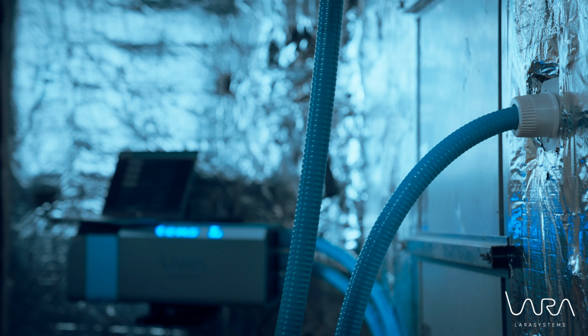The number and position of the spray heads are determined by the cross-section of the air duct, the design of the air duct network, and the volume of treated air. Under an air volume of 40,000 cubic meters per hour, the use of 1 blue pipe is generally sufficient. However, for air volumes exceeding 40,000 cubic meters per hour, or in the case of a branching air duct network, the use of a second, optional pipe may also become necessary.